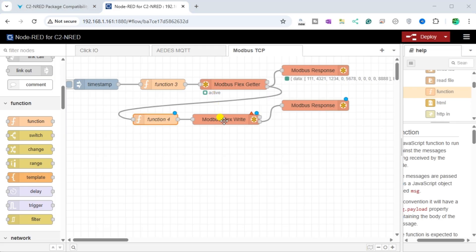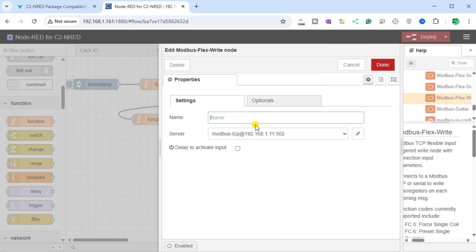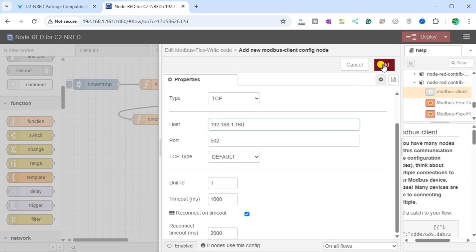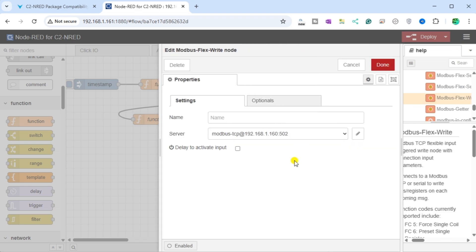The red triangle on the Modbus FlexWrite node means we must set up this node or provide additional information. Double-click on the node — the red box indicates we must add the Modbus client so it knows where to send the instructions set in the Function node. Add a new Modbus client. Our type will be TCP and our host will be the IP address for the Click PLUS PLC. Our port will be set to 502, which is the default. All other settings will be left as their default. Select Add. Our Modbus FlexWrite node is now set to communicate with our Click PLUS PLC. Select Done.